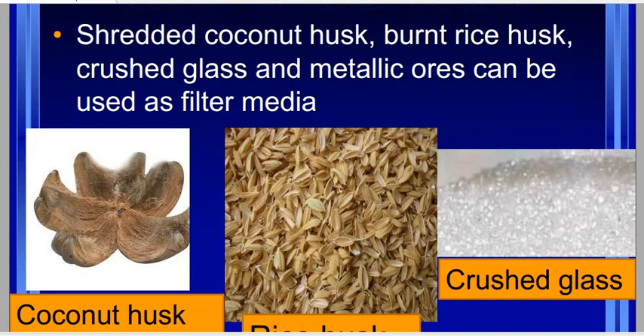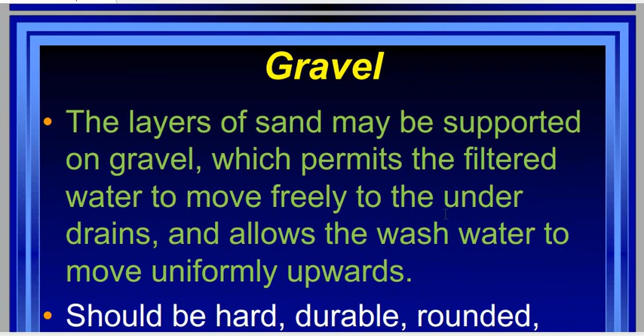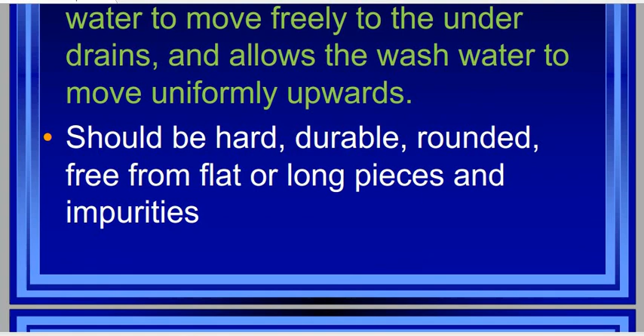The filter media should be supported by a base material, which is gravel. The layers of sand may be supported on gravel, which permits the filtered water to move freely to the under drains and allows the wash water to move uniformly upwards. The sand should be placed over the surface of the gravel. The under drains means the collecting pipes, and the wash water means the back water, moves uniformly in the upward direction. Gravel should be hard, durable, rounded, and free from flat or long pieces and impurities.